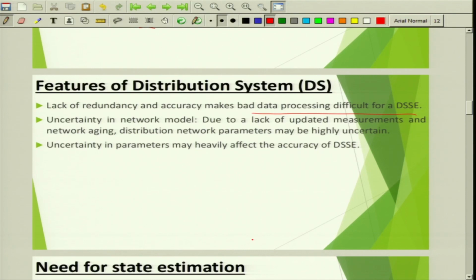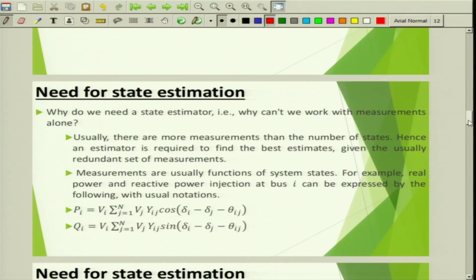Uncertainty in network model. Due to a lack of updated measurements and network aging, distribution network parameters may be highly uncertain. So this is another challenge actually. So because aging transformers and cables, aging is another factor where distribution network parameters may be highly uncertain, and uncertainty in parameters may heavily affect the accuracy of distribution system state estimation. So see, many vital challenges that one sees. And why do we need a state estimation? That is, why can't we work with measurements alone? You see, usually there are more measurements than the number of states, hence an estimator is required to find the best estimates given the usually redundant set of measurements.